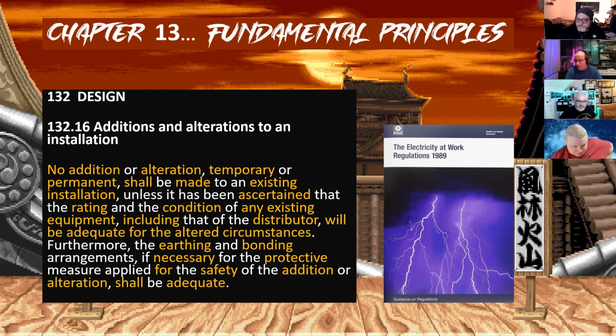This is an important one - well, they're all important, but this is a good one. No addition or alteration, temporary or permanent, shall be made to an existing installation unless it has been ascertained that the rating and condition of any existing equipment, including that of the distributor, will be adequate for the altered circumstances. Furthermore, the earthing and bonding arrangements, if necessary for the protective measure applied for the safety of the addition or alteration, shall be adequate.